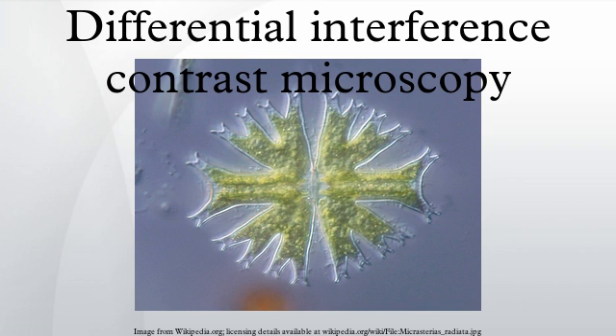Image quality, when used under suitable conditions, is outstanding in resolution and almost entirely free of artifacts unlike phase contrast. However, analysis of DIC images must always take into account the orientation of the Wollaston prisms and the apparent lighting direction, as features parallel to this will not be visible. This is, however, easily overcome by simply rotating the sample and observing changes in the image.